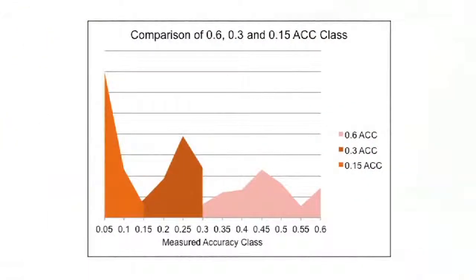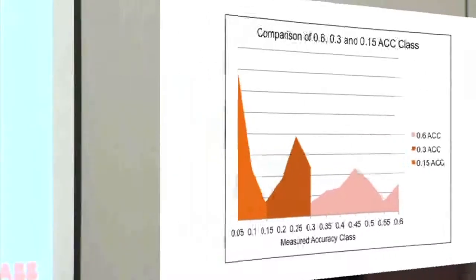We also test them at 100% of nominal current. So in that case of a 200:5 CT, we'll test them at 200 amps. You can see that the median right there is about a 0.25% accuracy. Okay, just barely inside the range of 0.3%. Okay, still pretty accurate, but you can see it's still near the top of where the 0.3% accuracy is. And then we tested our high accuracy CTs for test data, and you can see that the median falls at 0.05 and below, so they become much more accurate.